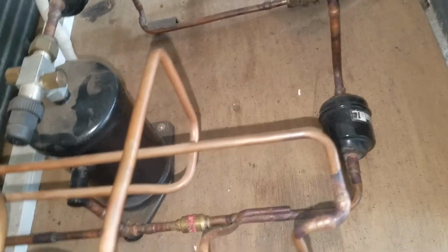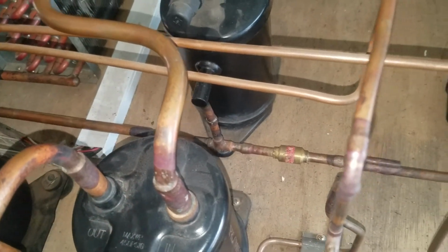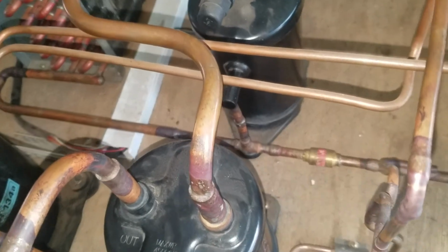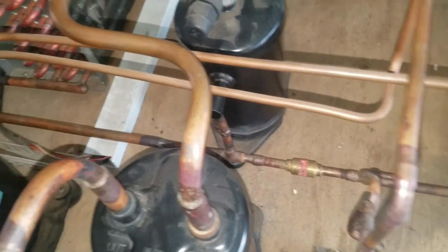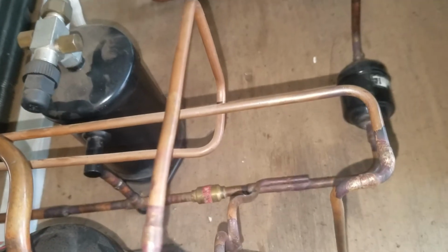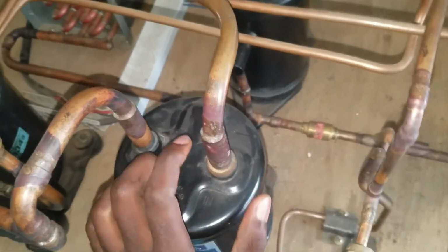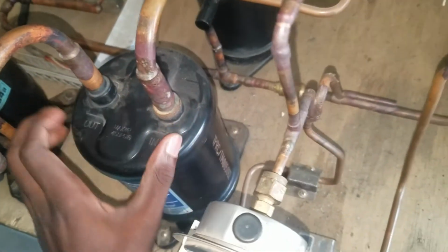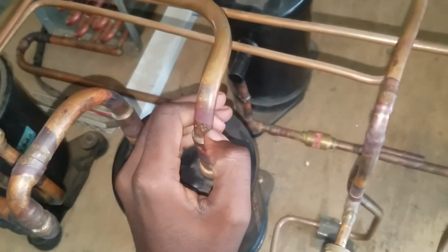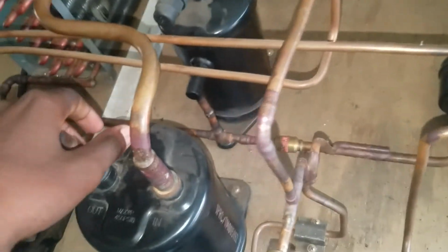Accumulator, it is a device. This is accumulator. You are seeing this is accumulator. The accumulator is a device which will prevent the compressor from sucking the liquid refrigerant, because in the evaporator you cannot be sure that the refrigerant is evaporated 100%. There is some liquid that remains in it. So to be sure that no liquid refrigerant enters the compressor, we put an accumulator. So guys, there are many other devices that can be added in this system, so that we can get what we want.